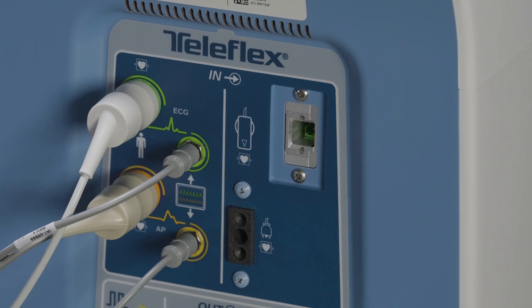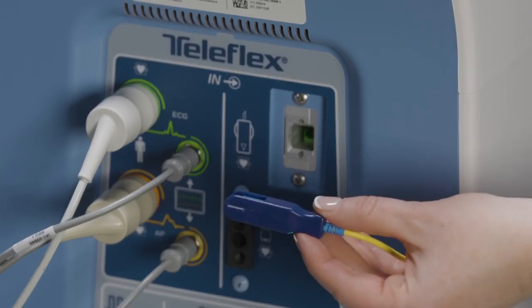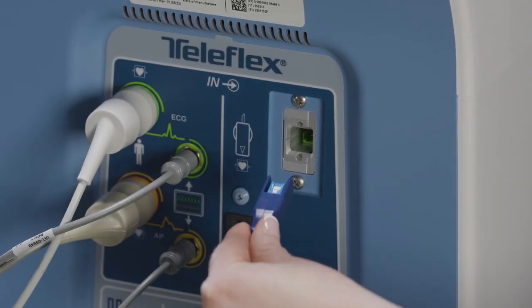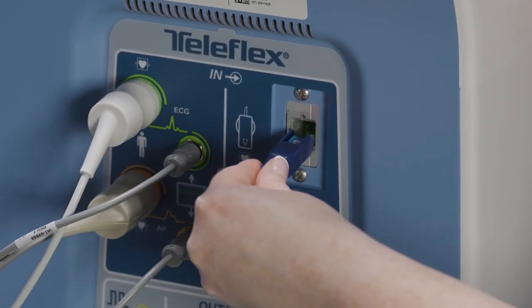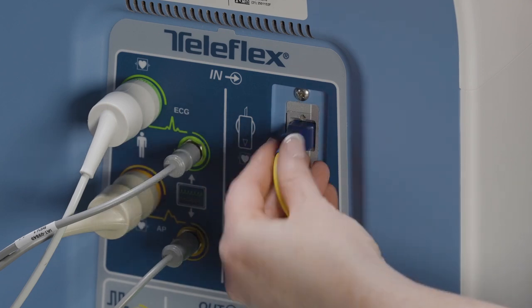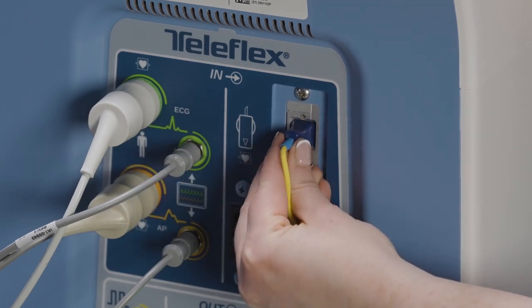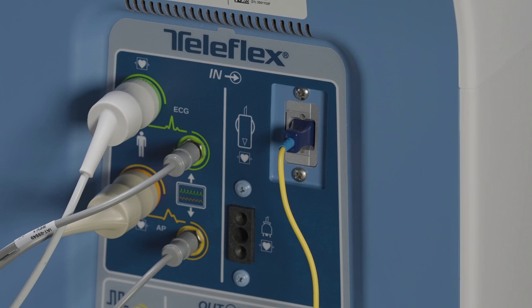The connections located on the right side of the dark blue area contain the balloon connection and the SimpleConnect fiber optics catheter AP sensor. The SimpleConnect fiber optic sensor will only fit one way. The seam of the connector should face upward. Push the slider gently into the receptacle until it clicks. A 2-beep tone will be heard when the sensor is properly connected.